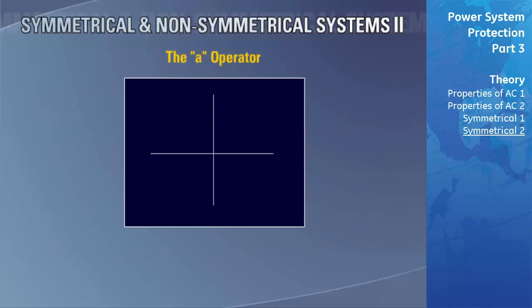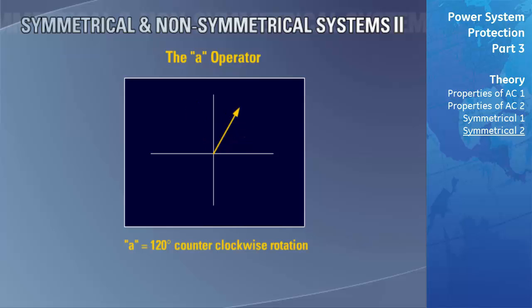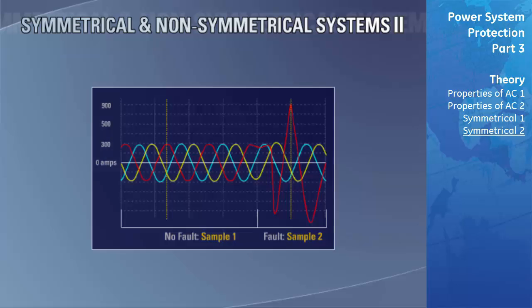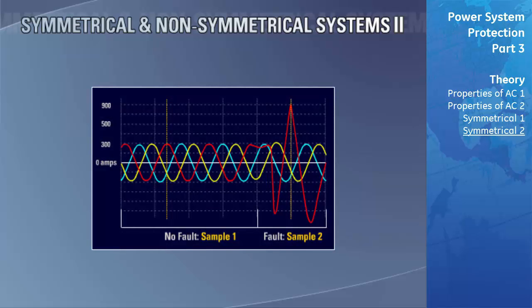The A operator shifts a vector by 120 degrees counterclockwise, similar to how the J operator in the complex plane shifts a vector by 90 degrees counterclockwise. The A-squared operator shifts a vector by 240 degrees counterclockwise. Let's see how Fortescue's formulas work under a real-world fault condition, using waveform data captured by a GE Multilin SR760 feeder management relay.